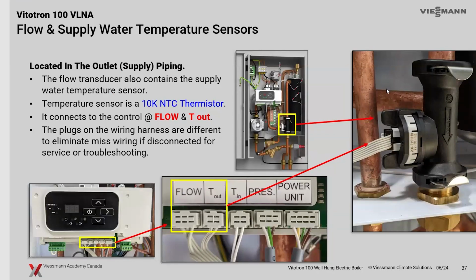We had talked about the temperature in, the return temperature, already. Now we have the supply temperature out. So we have 2 things here. This one little device feeds back through a little ribbon cable, both flow, so it gives us a flow rate in gallons a minute, and it also senses the supply temperature going out. So we know flow, we know temperature in, temperature out. It's very easy to calculate things like BTUs, et cetera.